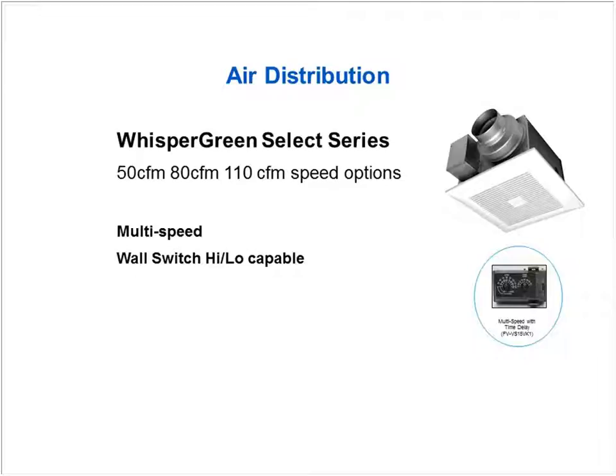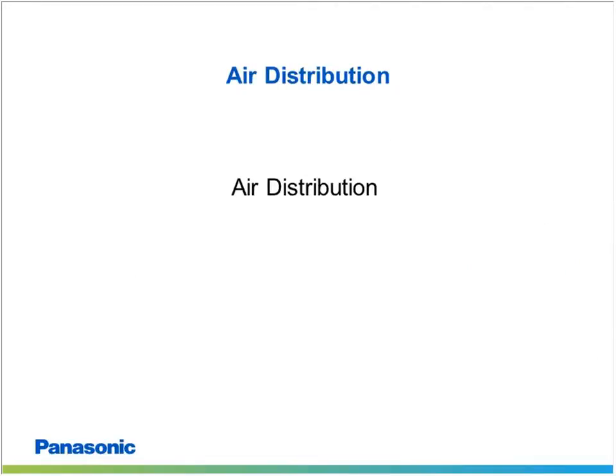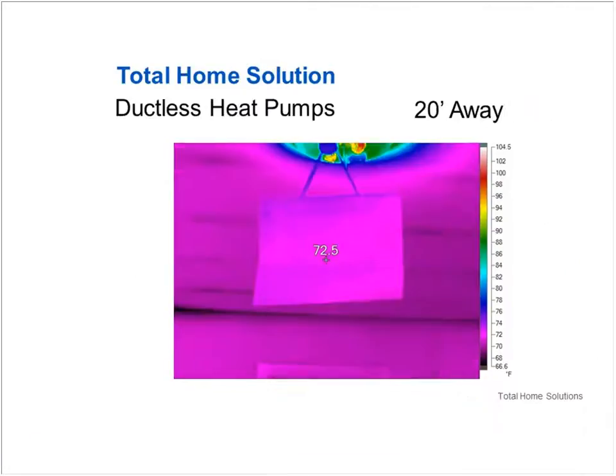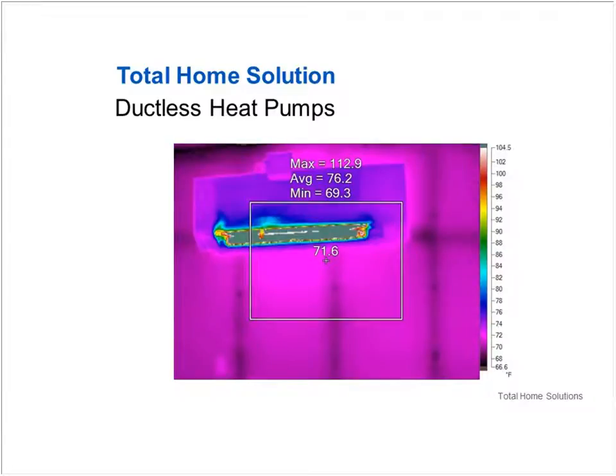So there's a couple of ways that we've been doing it. We have a number of builders out here. In particular, probably the big one is D.R. Horton down in Portland. D.R. Horton takes these Whisper Green Selects, and they set the variable speed at 30 CFM, and they'll literally set them on that ceiling area right above the indoor wall unit.